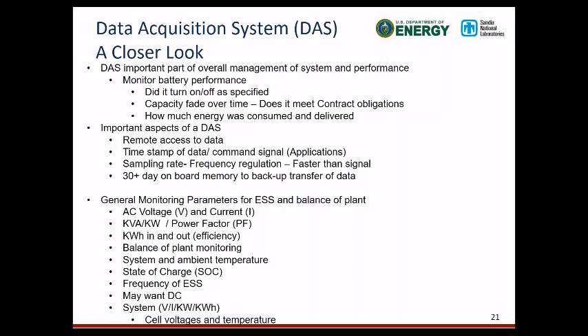Sampling rate is a very large consideration. If you're doing frequency regulation, you need very fast monitoring, so your sample rates are down at the seconds or sub-second level. If you need harmonics, you're at sub-cycle levels. If you're doing more of an arbitrage application, you can look at 1-minute and 5-minute data. So sampling rate depends on what applications you're doing with your energy storage.